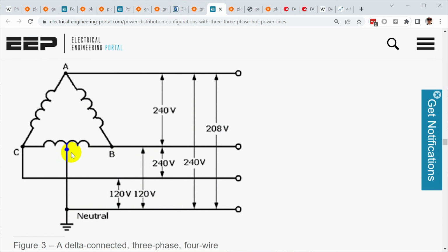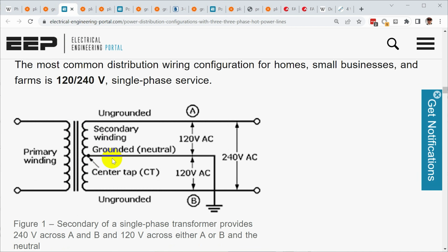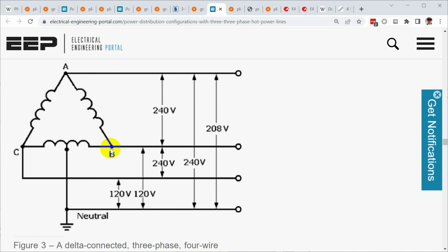Now, with the rotary phase converters, these are actually A and B, not C and B. At least that's the way they're labeled on mine. It may vary on yours. The point being that you still have three phases, A, B, and C, that are 240 volts, 120 degrees out of phase with one another, but one of those 240 volt phases is center tapped. Now, in the case of the rotary phase converter, this is the input. You already have this configuration coming from the wall with the center tap transformer, and you're simply feeding that into the rotary phase converter, and it is producing the third leg. I believe on the American Rotary ones, this is labeled C, so just don't worry about the letters, but this is what's happening.